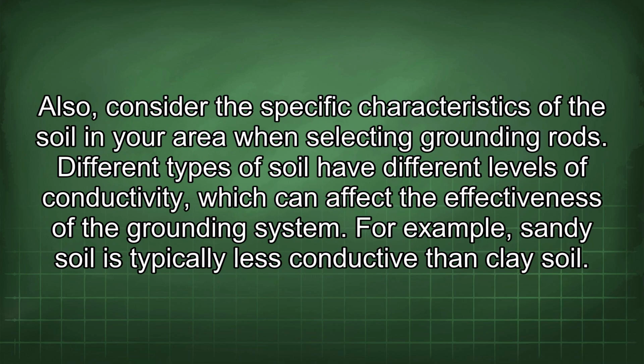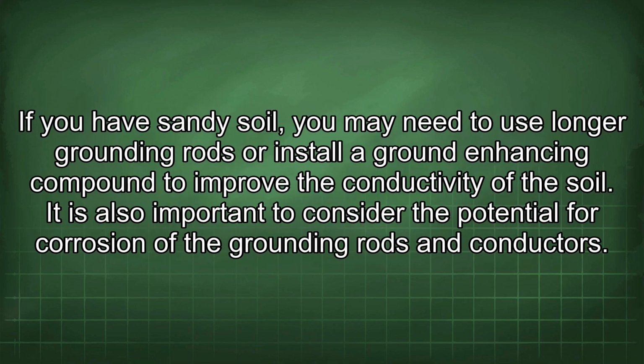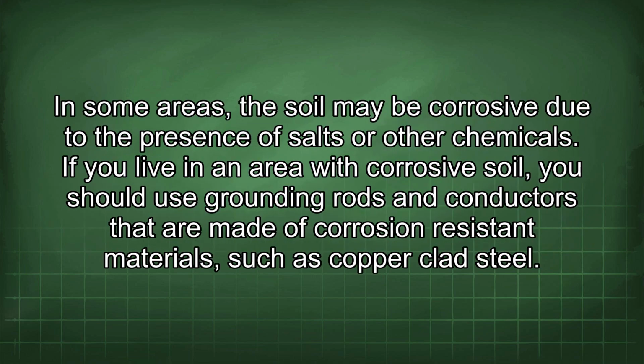Also, consider the specific characteristics of the soil in your area when selecting grounding rods. Different types of soil have different levels of conductivity, which can affect the effectiveness of the grounding system. For example, sandy soil is typically less conductive than clay soil. If you have sandy soil, you may need to use longer grounding rods or install a ground-enhancing compound to improve the conductivity of the soil. It is also important to consider the potential for corrosion of the grounding rods and conductors. In some areas, the soil may be corrosive due to the presence of salts or other chemicals. If you live in an area with corrosive soil, you should use grounding rods and conductors that are made of corrosion-resistant materials, such as copper-clad steel.